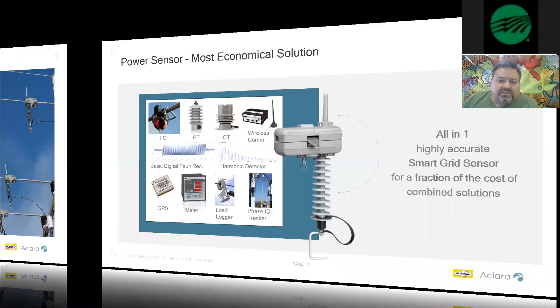As far as what it replaces, it replaces a fault current indicator, so it's much more significant as far as data goes than an FCI. With an FCI, once it trips, you have to drive down the lanes with binoculars looking for flags and flashing lights. These sensors have communications built in, either Wi-Fi or cellular, and will blast the data back to you. If you have multiple sensors on each feeder, it will geolocate the fault for you, so the crew drives straight to where they know the fault has been located.